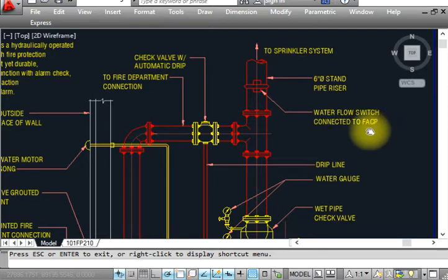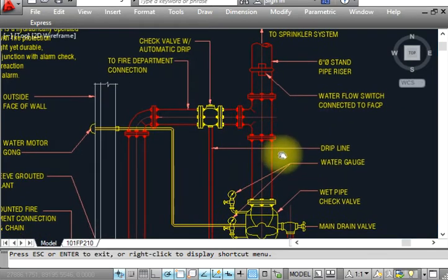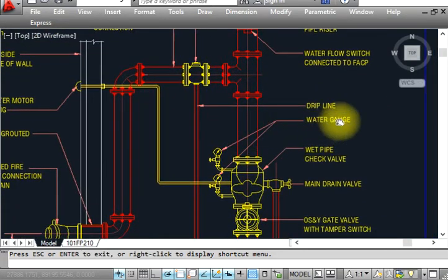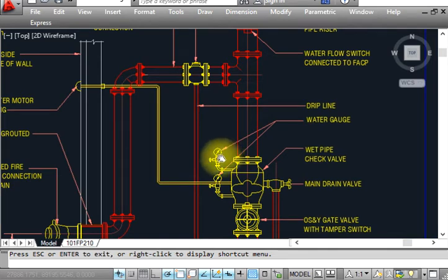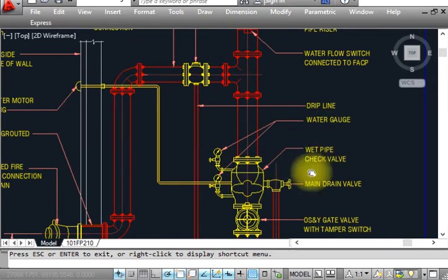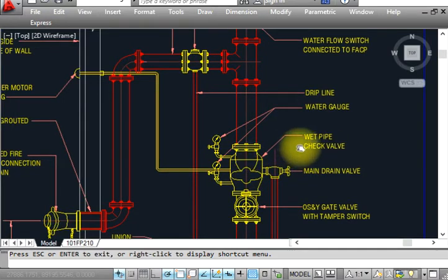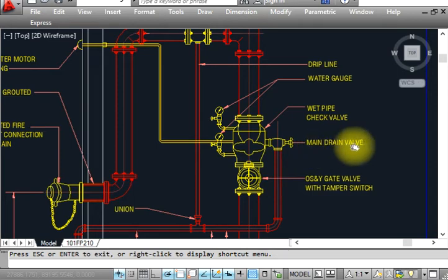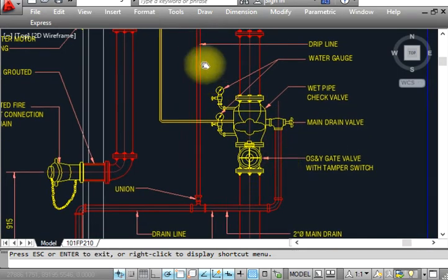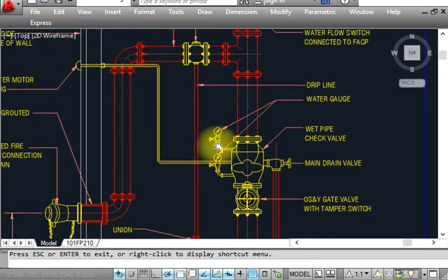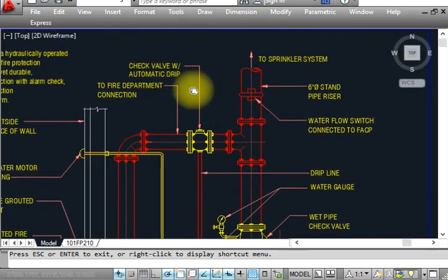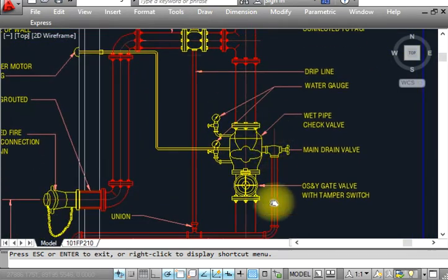Water flow switch is connected to the FACP. This is the drip line. This is the water gauge. This is wet pipe check valve. This is the drain valve. We have to drain the water from this, so there's a drip check valve automatically.